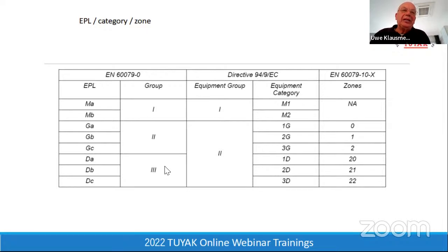This means that for category 3 equipment, you can use it in zone 2 or in zone 22 in this case. Zone 2, 3G, GC.